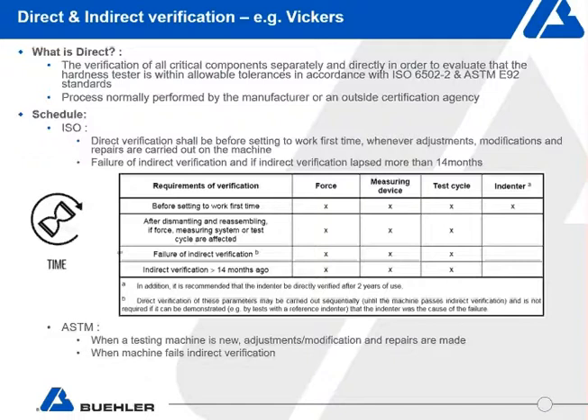For ASTM, it does specify that for a new machine, as well as whenever any adjustment or repairs are made, or when your machine fails the annual indirect verification, when you've got an external certification agency or the manufacturer looking at your tester.